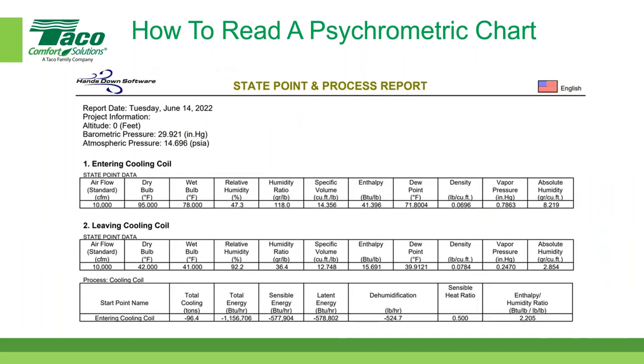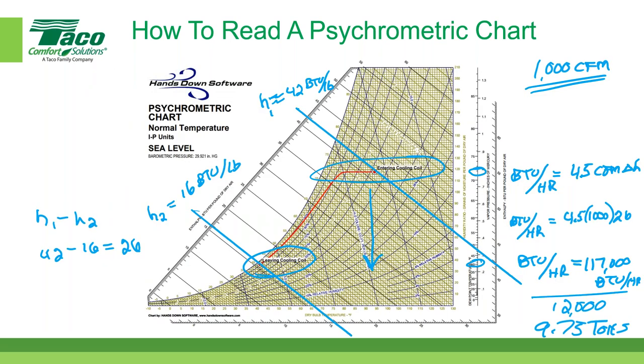Only this time I did it for 10,000, which should be roughly 10 times that amount. If you'll notice, I did this calculation based on 10,000 CFM. Here's my entering air, 95 degrees dry bulb, 78 wet bulb. Here's my dew point temperature, 71.8. And what did I estimate the dew point temperature? About 72, I think. Go back here. Yeah, about 72.